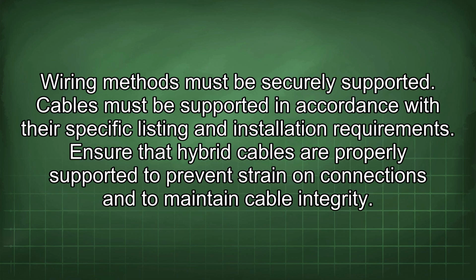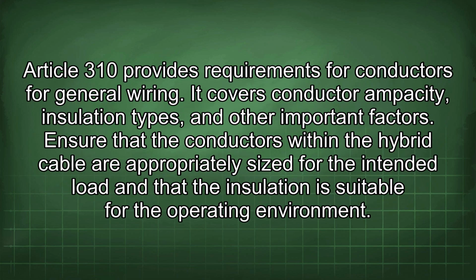Wiring methods must be securely supported. Cables must be supported in accordance with their specific listing and installation requirements. Ensure that hybrid cables are properly supported to prevent strain on connections and to maintain cable integrity. Article 310 provides requirements for conductors for general wiring. It covers conductor ampacity, insulation types, and other important factors. Ensure that the conductors within the hybrid cable are appropriately sized for the intended load and that the insulation is suitable for the operating environment.